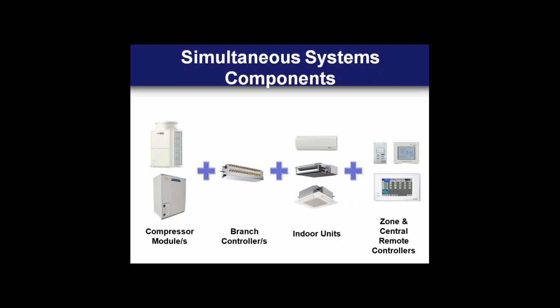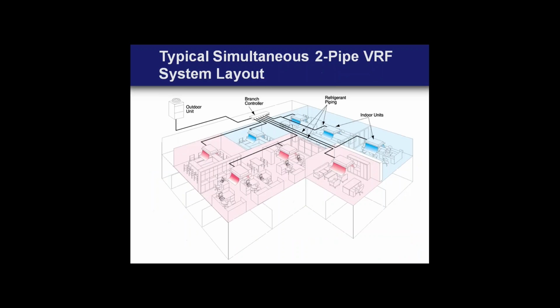You can go a step further, which most people do in most applications, and apply what we call zone remote controllers that you can locate on the wall, give you interface capability to the indoor units in the system, and also provide remote sensing capability closer to the occupied zone. And then you can go up to higher levels to what we call system controllers that can control multiple systems with multiple indoor units, and then even a step further into LonTalk and BACnet gateways to integrate these systems into conventional building management systems by third parties if need be.